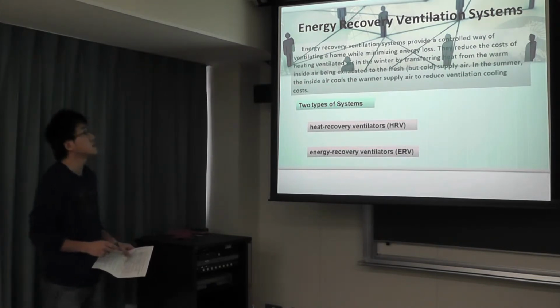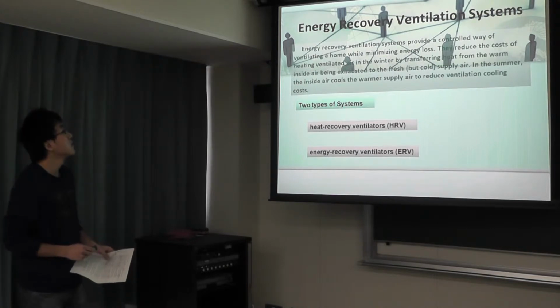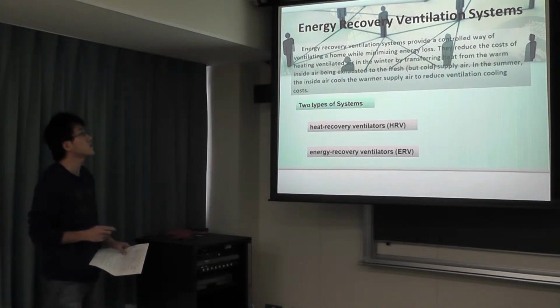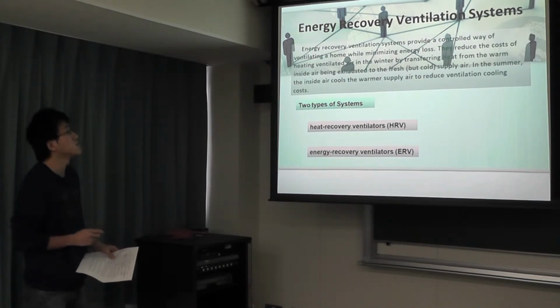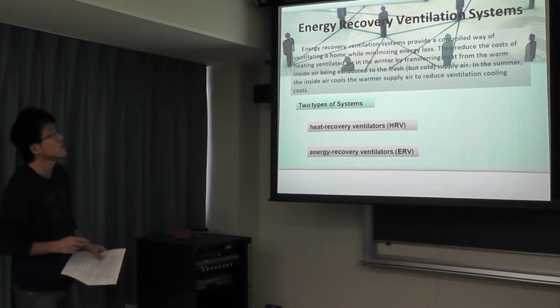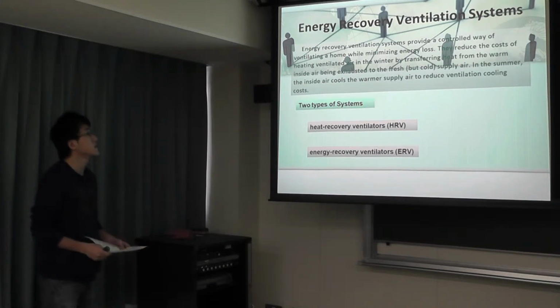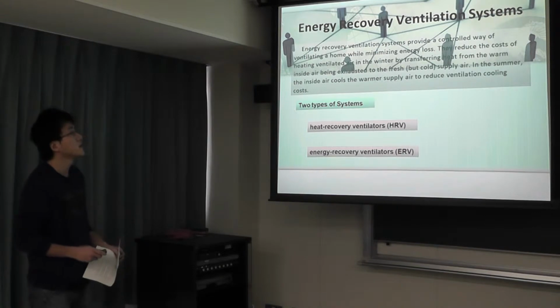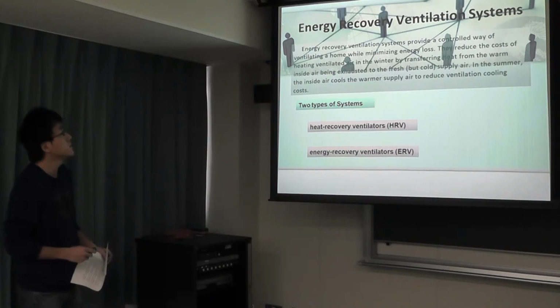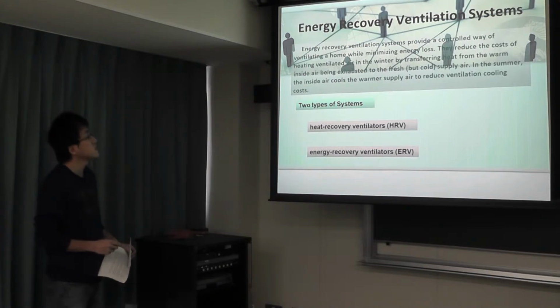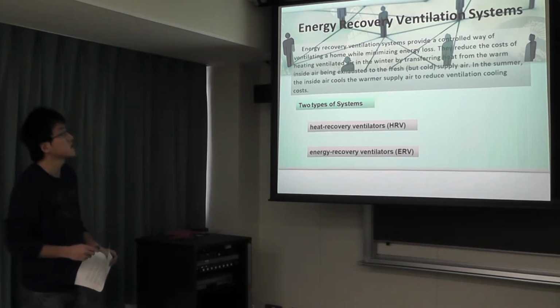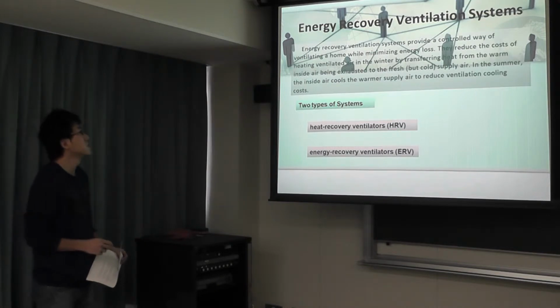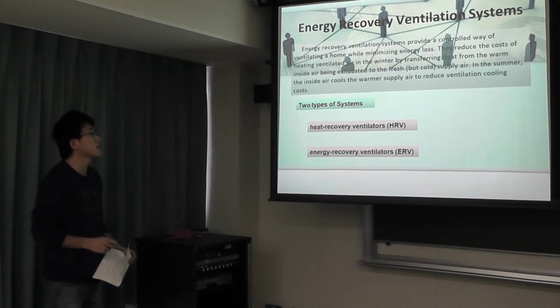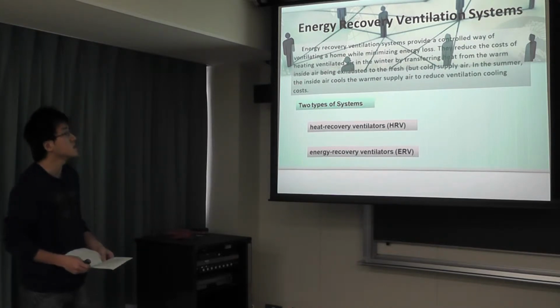Energy recovery ventilation systems. Energy recovery ventilation systems provide a controlled way of ventilating a home while minimizing energy loss. They reduce the cost of heating ventilated air in the winter by transferring heat from the warm inside air being exhausted to the fresh supply air. In the summer, the inside air cools the warmer supply air to reduce ventilation cooling costs.